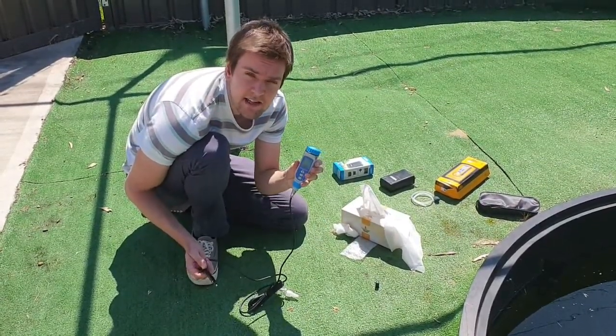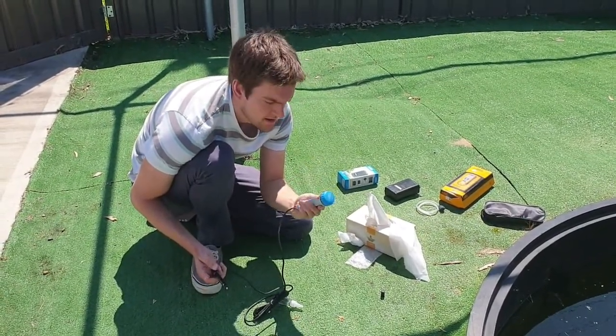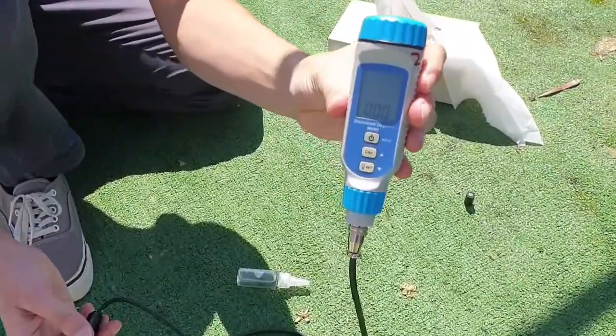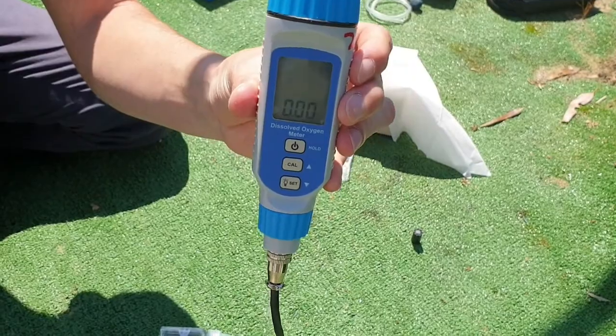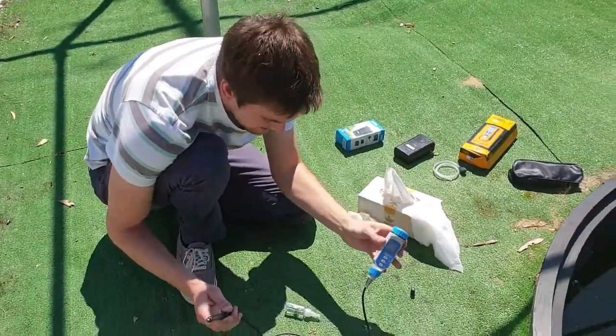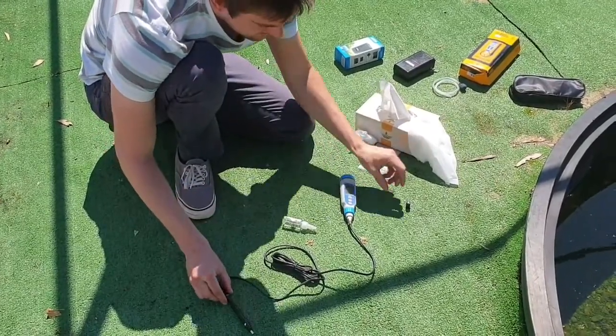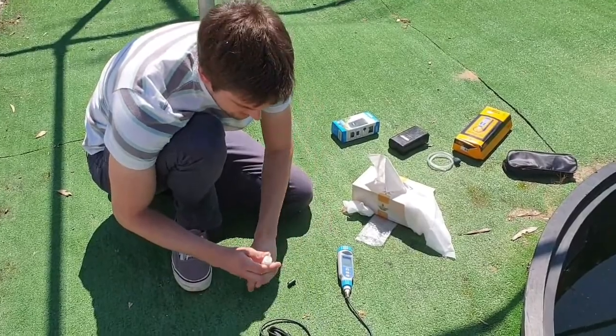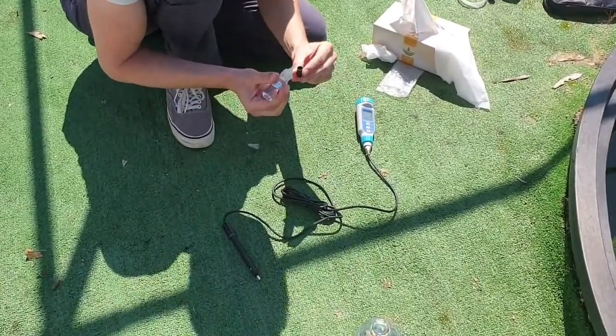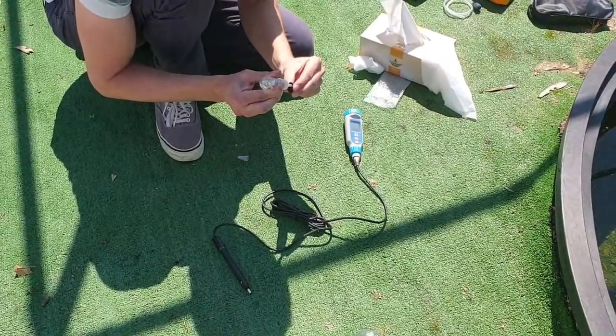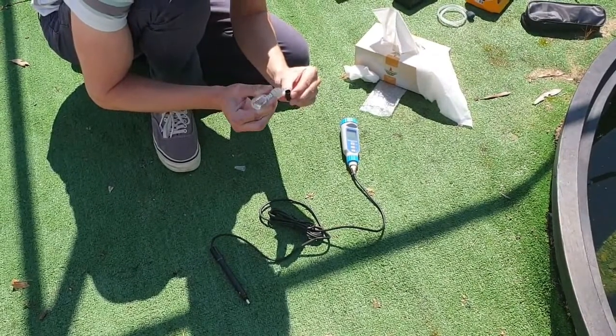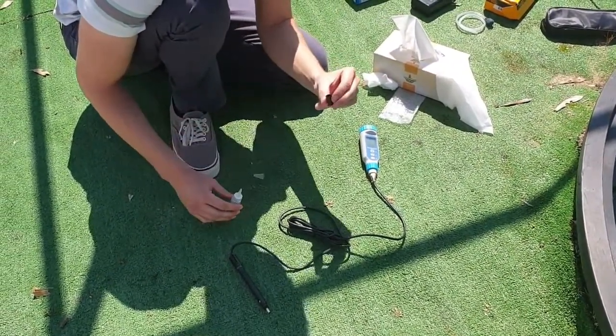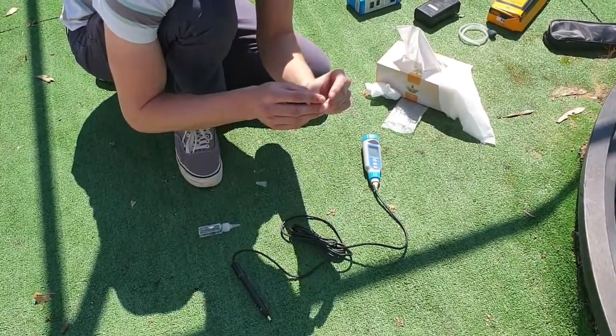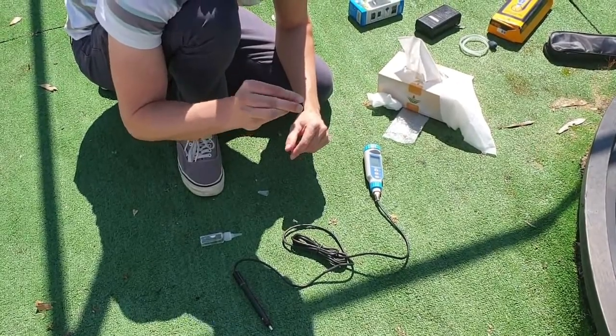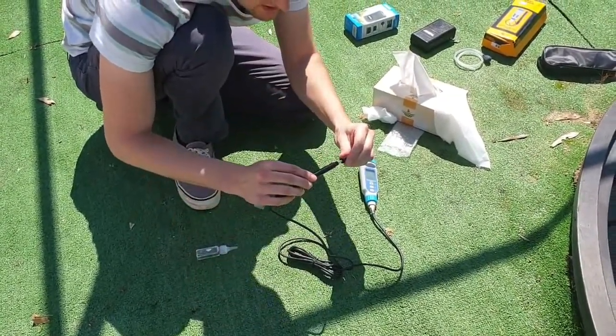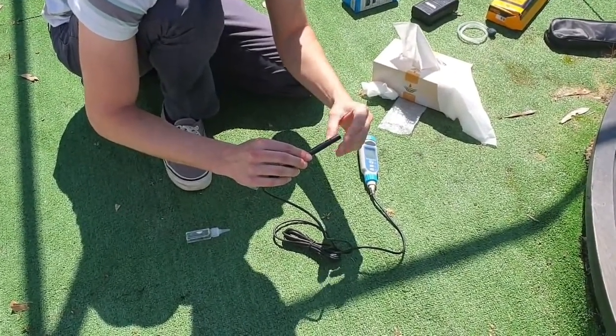Following the pass message from the 0 point calibration, we can now see that the probe has automatically entered into the 1 point calibration, as shown by the 1 flashing there. So for the 1 point calibration, the first thing we need to do is refill the probe with electrolyte. So we take the cap off the electrolyte, again apply 3 to 4 drops of electrolyte into the probe head, making sure there's no bubbles inside the probe head, and if there is, slightly tapping the probe head or giving it a shake to remove the air bubbles. Then re-screwing the probe head onto the probe.